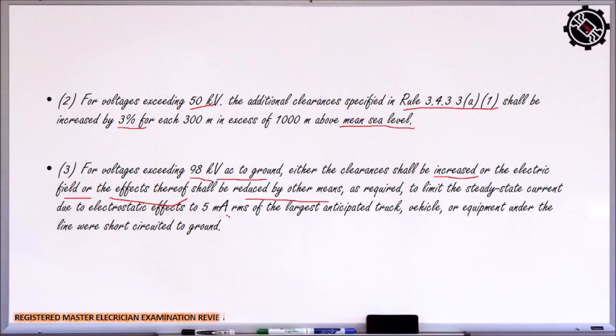So the acceptable is 5 milliamperes, no? 5 milliamperes. So kunyari pag may dadaan doon na truck, yung ma-feel niya na current is below, no? Equal or below 5 milliamperes. If lalagpas dyan, then you must now increase the vertical clearance or cover the conductor, depending on which is much applicable. Kasi kapag kinover natin ng conductor, madadagdagdagan niya ng sag. Aside from having the electrostatic effect, ang magiging problema mo naman ngayon is baka sobrang baba na ng conductor, pwede nang matamaan ng mga truck. Okay?